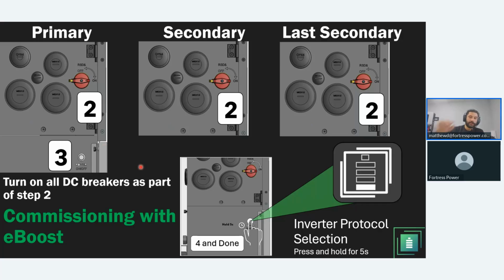Then you're going to turn on the battery, and in the eBoost case, you're going to press and hold it for 2 seconds. It's going to boot up, and if you have multiple batteries in parallel, that's going to boot up the other batteries in sequence. And then after that, you're going to make sure that the inverter protocol is selected correctly on the eBoost. By default, this is going to come compatible with the Sol-Ark inverter and NV inverter, but I always include this process just to make sure, so that if in the process you tapped it and changed something, you can always go back to these instructions.